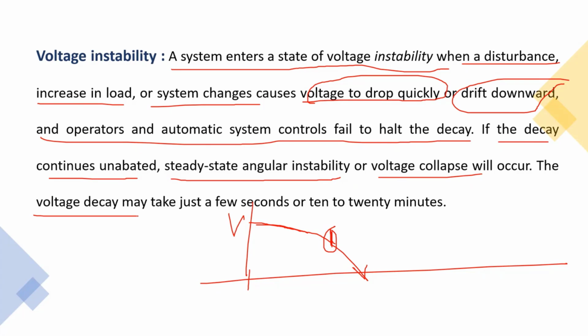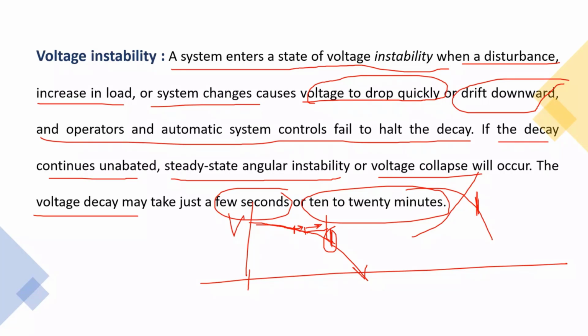So this voltage decay may take either a few seconds or 10 to 20 minutes. It depends on what point you are lying at. Let us say you are lying at this point, and the load is increasing swiftly, it is further increasing, and voltage is decreasing in this way. As soon as you reach this point, whatever we call the knee point or knee voltage, at this point your generator, whatever the reactive power sources in the system, will not be able to sustain the transfer of active power into the system. The electromagnetic force that was required to hold the system is at its own limits.